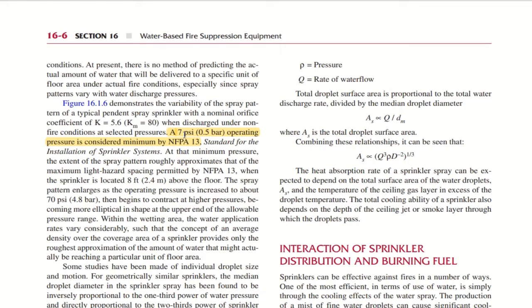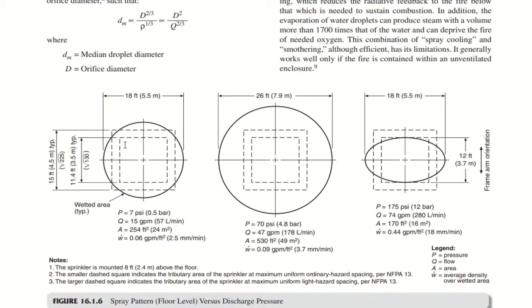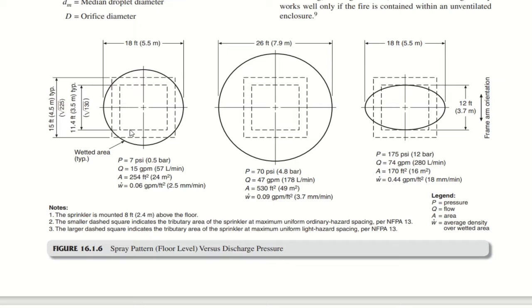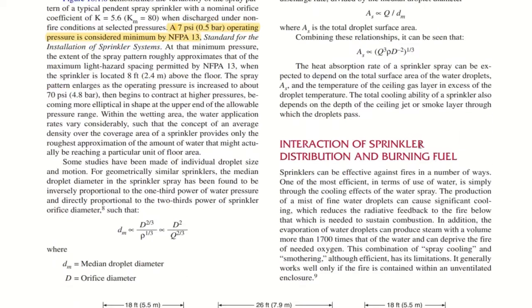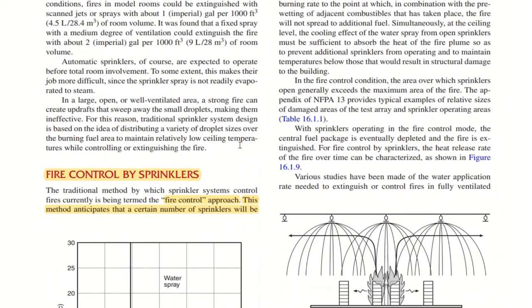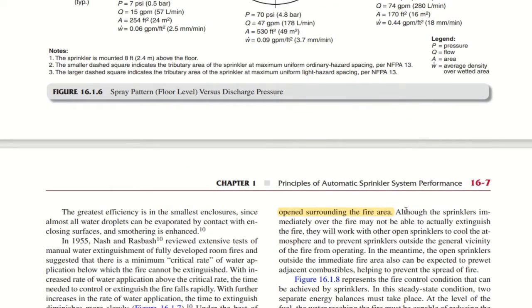As per NFPA 13, a 7 psi operating pressure is considered minimum. Here you can see the spray pattern versus discharge pressure, and you can see various spray patterns here. Apart from this, on the next page we have the fire control by sprinklers. The traditional method by which sprinkler systems control fires is currently termed the fire control approach. Whenever you see a question related to the fire control approach, you just come to section 16 chapter 1, you will find the answer. This method anticipates that a certain number of sprinklers will be opened surrounding the fire area.